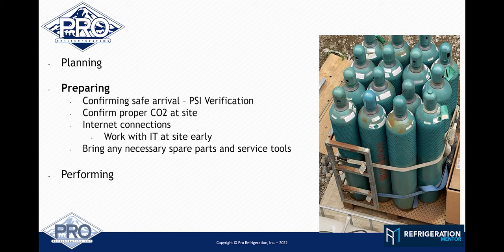Depending on where you are in the world, you'll get different cylinder bottles—some have a white line painted down to mark the tube, some have an S, and this is the first time I've seen one that actually says siphon on it; some just have a tag showing it's siphon. You need to understand the difference between a vapor CO2 cylinder and a liquid cylinder—when it says siphon, like in the photo, that means it's a liquid cylinder.